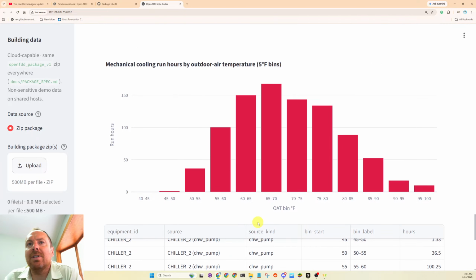Okay, where else can we go with this? So this looks like a normally distributed chart. Most of the data is in between this range. Shoulder season. Some of this can exist too because of the difference in the outside air temp sensor to the building's actual hardwired sensor.